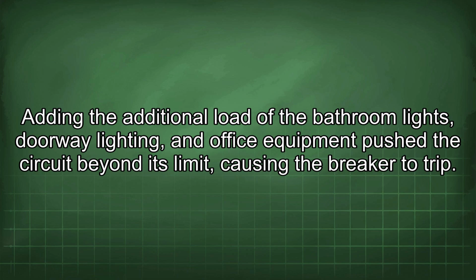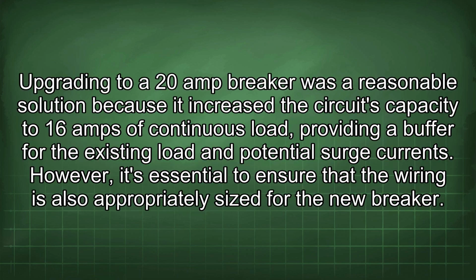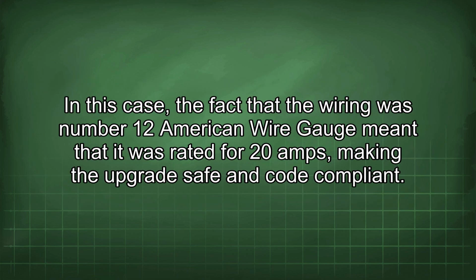Adding the additional load of the bathroom lights, doorway lighting, and office equipment pushed the circuit beyond its limit, causing the breaker to trip. Upgrading to a 20 amp breaker was a reasonable solution because it increased the circuit's capacity to 16 amps of continuous load, providing a buffer for the existing load and potential surge currents. However, it's essential to ensure that the wiring is also appropriately sized for the new breaker. In this case, the fact that the wiring was number 12 American wire gauge meant that it was rated for 20 amps, making the upgrade safe and code compliant.